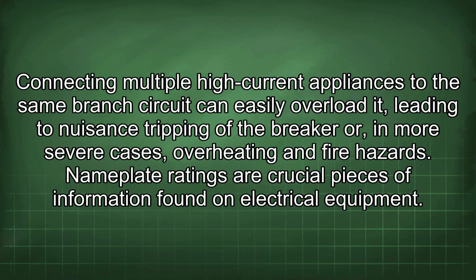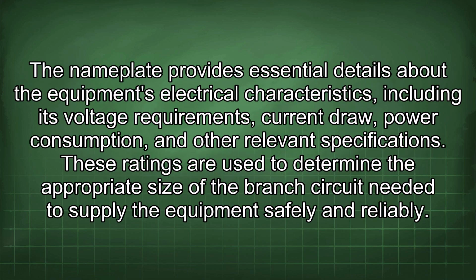Connecting multiple high-current appliances to the same branch circuit can easily overload it, leading to nuisance tripping of the breaker or, in more severe cases, overheating and fire hazards. Nameplate ratings are crucial pieces of information found on electrical equipment. The nameplate provides essential details about the equipment's electrical characteristics, including its voltage requirements, current draw, power consumption, and other relevant specifications. These ratings are used to determine the appropriate size of the branch circuit needed to supply the equipment safely and reliably.